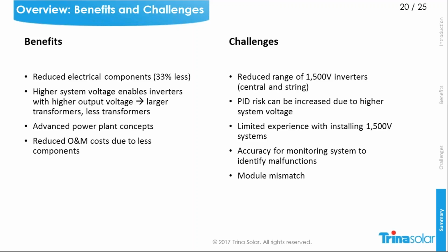The challenges are the product range for inverters and for combiner boxes, even if the technique is known, for example, from the railway industry. The risk of PID due to the higher system voltage, but this depends, as I said, on the location and on the system design. And the limited experience, especially now in Europe with 1,500 volt systems. The US and Asia were more open to 1,500 volt systems and have already installed some. In Europe, the number is still quite limited.